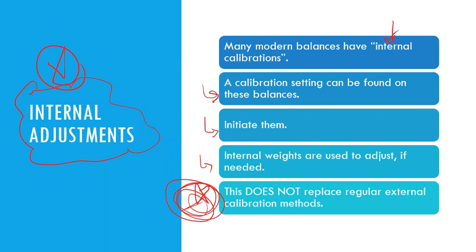So internal calibrations are great. Those are things that you can do just as a quick measure to make sure that you're in line. But I'm still, as a user, required to take these external calibration sets and put those calibration weights onto the balance pans and record those numbers to make sure they are in line with what needs to be there.